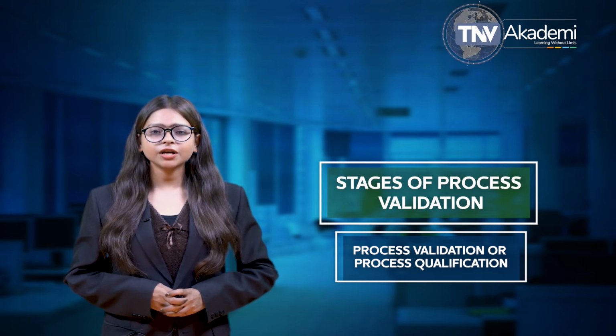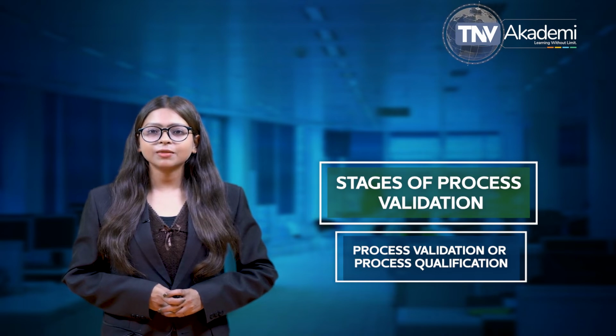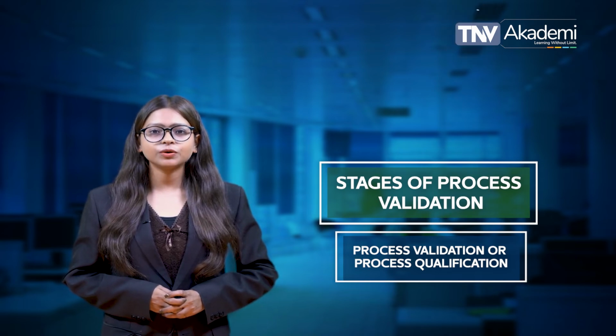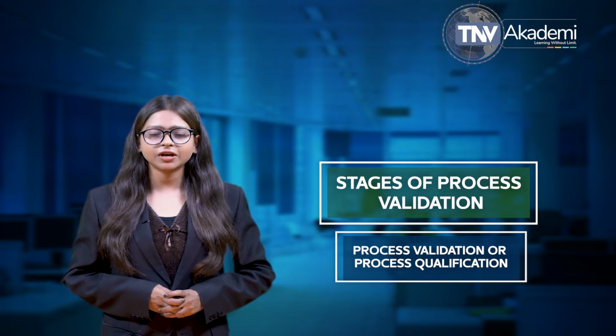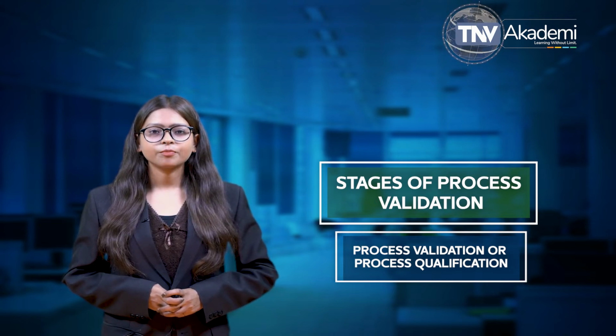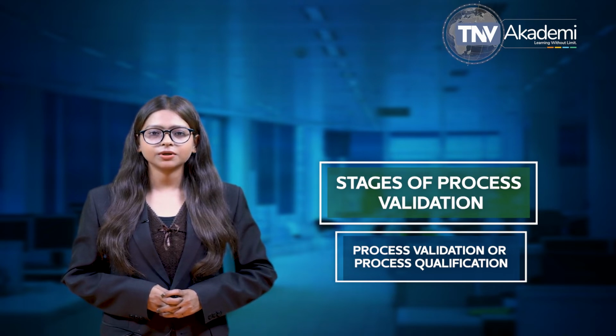Next, qualification of utilities and equipment should be conducted, such as making sure that they are built and installed in compliance with design specifications. Finally, process performance qualification should be executed through a protocol and documented in a report.